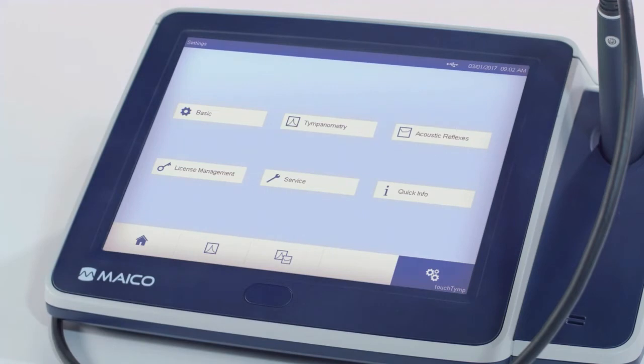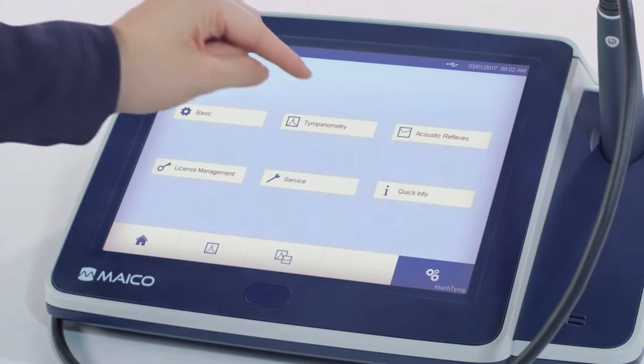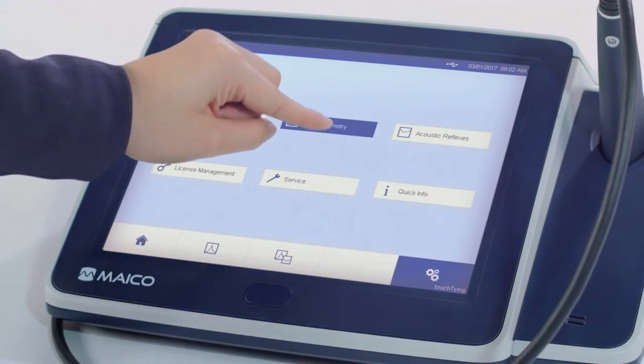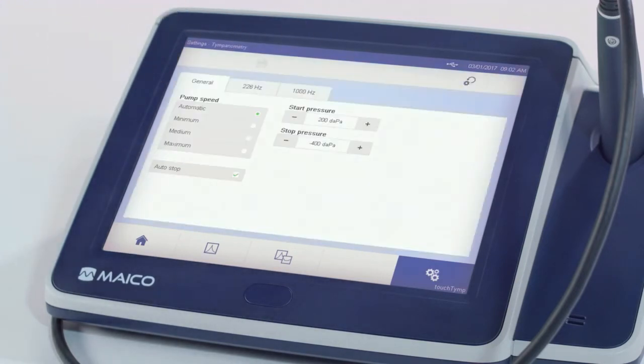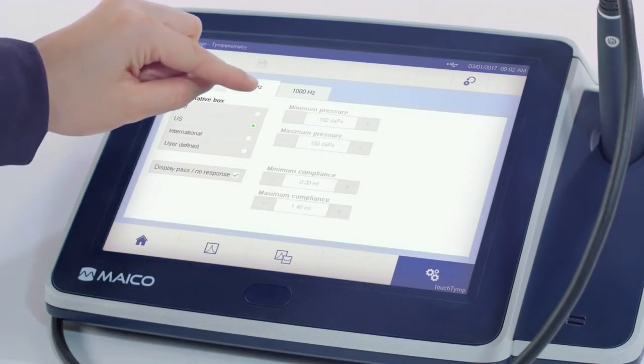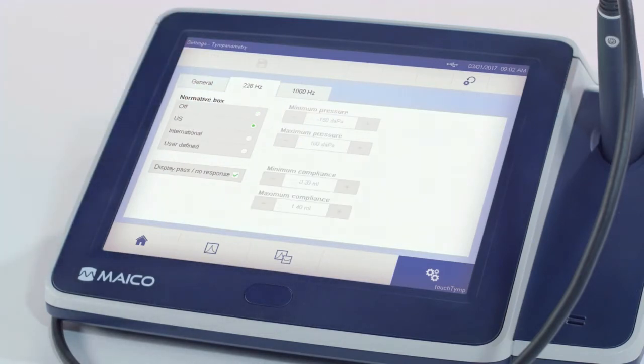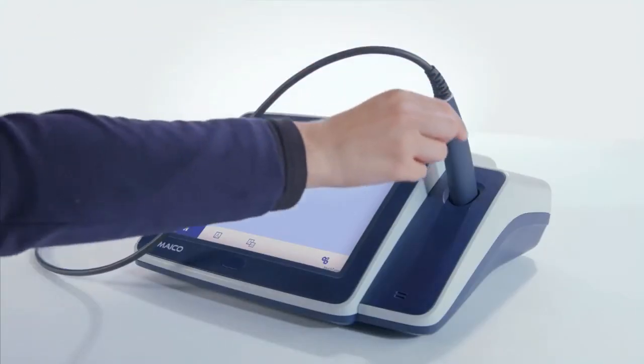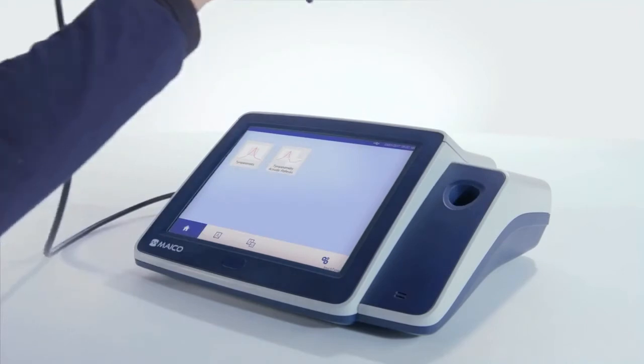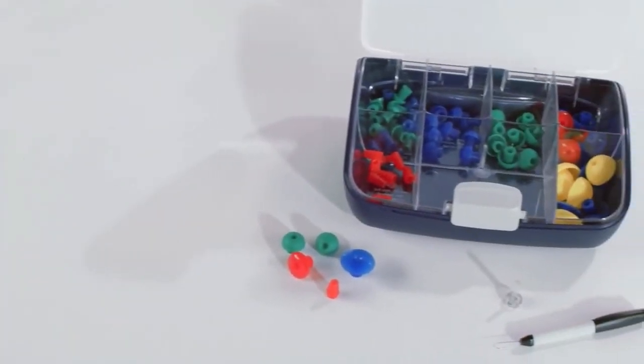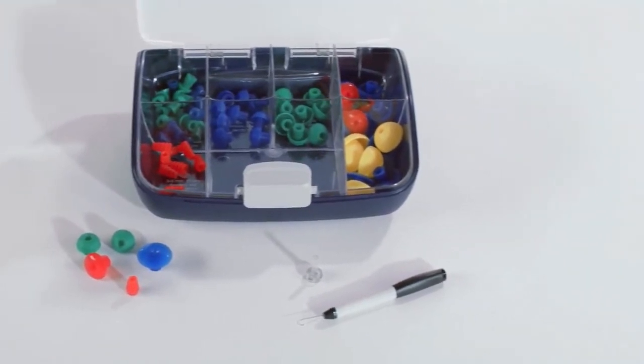The touchTymp has a variety of custom settings to modify the standard protocols within the device. Some examples include displaying a normative box for the tympanometry results, or a pass, no response indicator upon completion of the test. Take the probe out of the cavity to start the selected module immediately. The selection of the appropriate ear tip is necessary for the measurement to be completed.